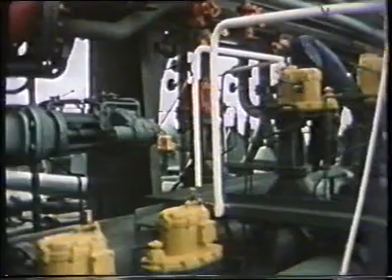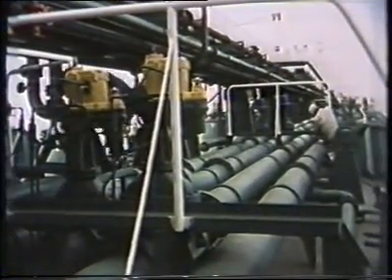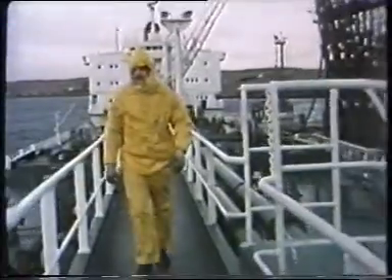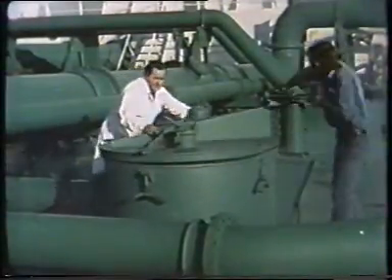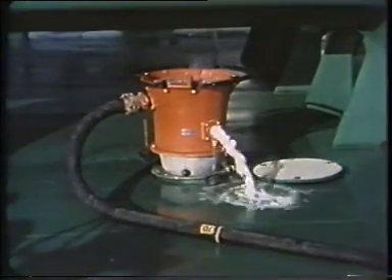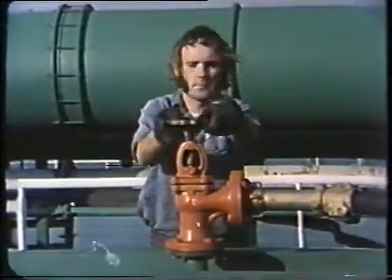When washing is complete, the tanks are repurged, all vents reclosed, and the system is brought back to pressure. A lot of maintenance is carried out on inerted ships, but for repair work inside tanks, obviously they must be thoroughly ventilated first. Gas freeing can be done in two ways: with portable fans, or with the IG system blowing air. For the first method, the individual tank is locked open, isolated from the IG main, and portable fans are mounted in the tank washing apertures either to suck out the IG or to blow in fresh air.